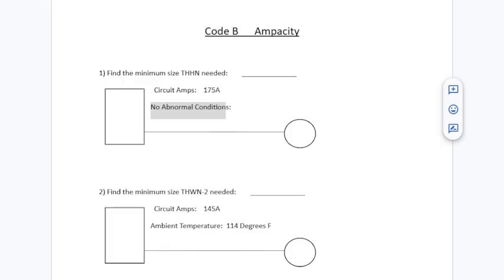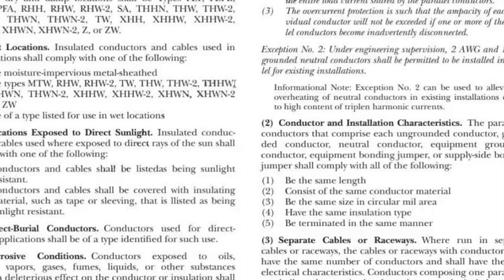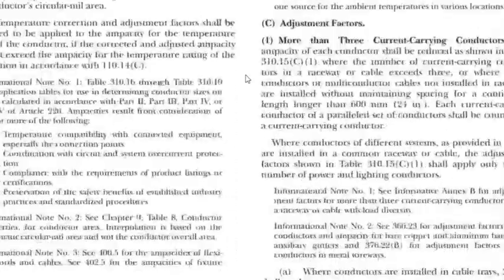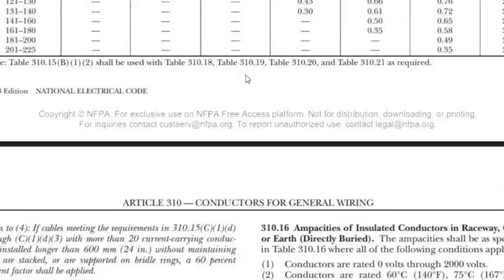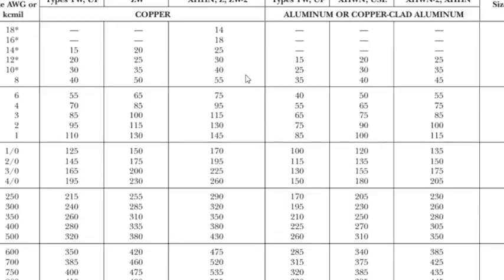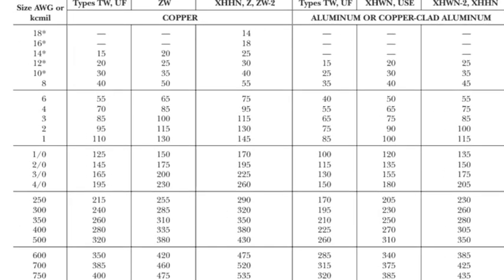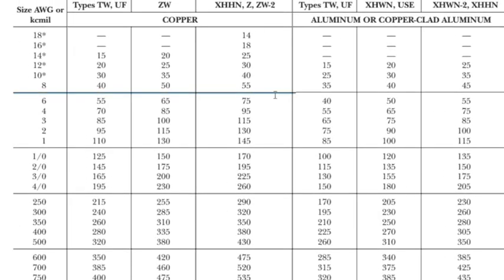But this question is asking me for a specific insulation. So we do that. It's still the same, right? Is it still a 2/0? I didn't look at it. Sorry to scroll down so fast. I don't like to do that when you guys are looking, but in the 75-degree column, the 2 aught is 175, and then in the 90-degree, it's 195. Oh, so it ends up being the same thing for either one.